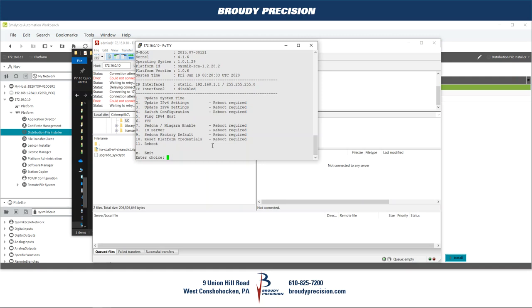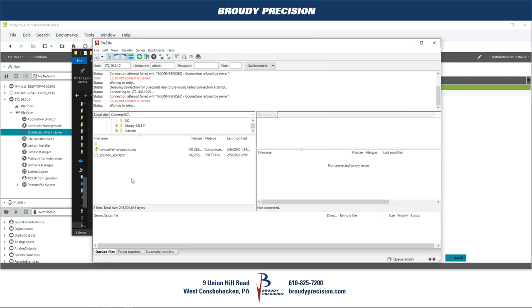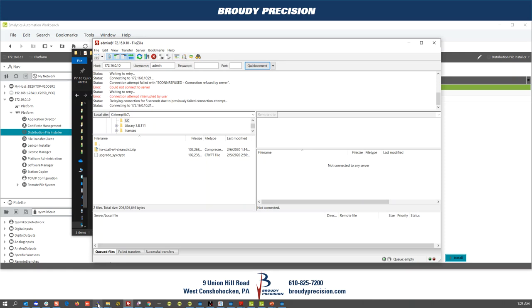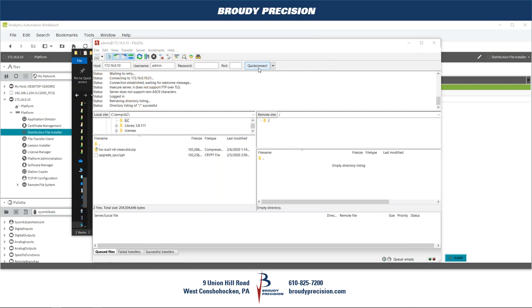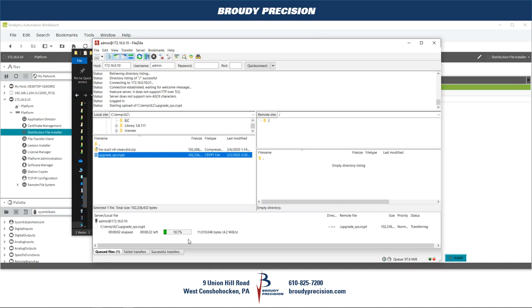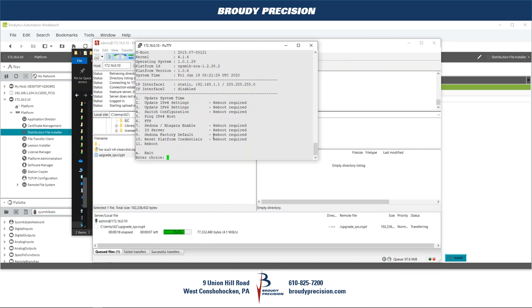After confirming the FTP enable option, we click Quick Connect and we are now logged into the controller via FileZilla FTP. The only folder is the root folder. At this point we copy the .crypt file over to the ILC 2050 — it is a 102 MB file so we wait for it to copy completely. Once that is done, we'll go back to shell and tell it to reboot.